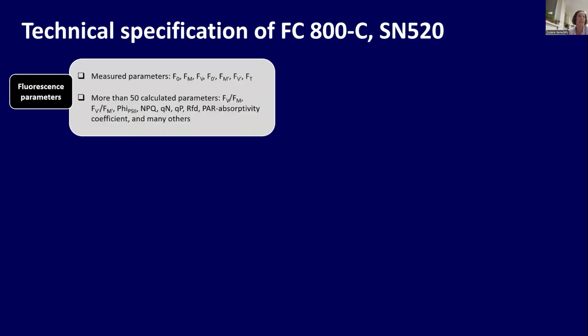This is a technical specification of your FluorCam. So the FluorCam, of course, is for measuring of fluorescence parameters. It can provide you different protocols and really a lot of parameters, more than 50, in a protocol called quenching analysis. I would like to divide these parameters to something like absolute or measured parameters. These are parameters called F0, Fm, Fv, or Ft. These parameters are actually the images you measure in reality. And from this, by mathematical combination of 2 or more images, you can calculate so-called calculated parameters.